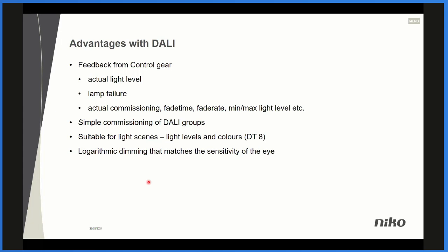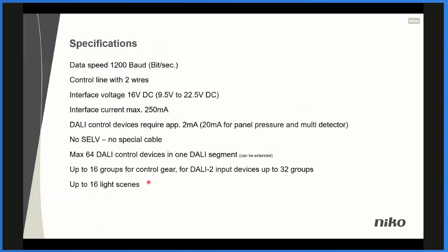The dimming curve that we have with the DALI luminaires is actually matching the sensitivity of the eye, because it's not a linear dimming, it's a logarithmic dimming. So that is also one of the great advantages of DALI. The data speed on the DALI bus is very, very low, around 1200 baud, and that doesn't matter.